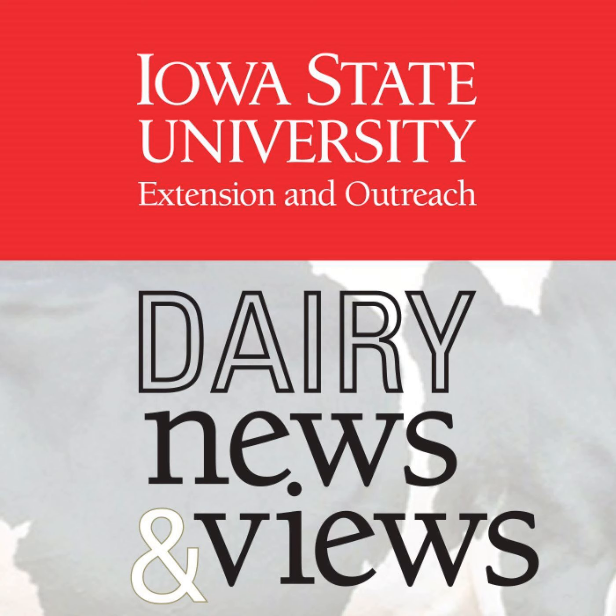And so, the longer this cow is affected by heat stress, the more time they spend trying to cool off instead of resting in the stalls. And so to counter this, the research indicates you want to shoot for a minimum airspeed of about 200 feet per minute, or about 2.25 miles per hour, and you want to measure that in the stall resting area. And there's a number of different ways to get those airspeeds. You can use the recirculation fans that just hang above the stalls. You can use tunnel ventilation, cross ventilation, that high volume, low speed fans. There's lots of different options to do that, but they each have their pros and cons, things you have to take into consideration when you install those.